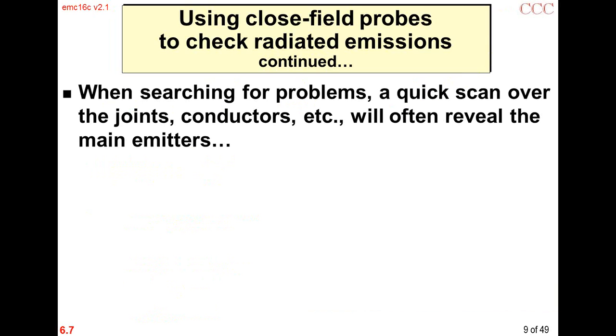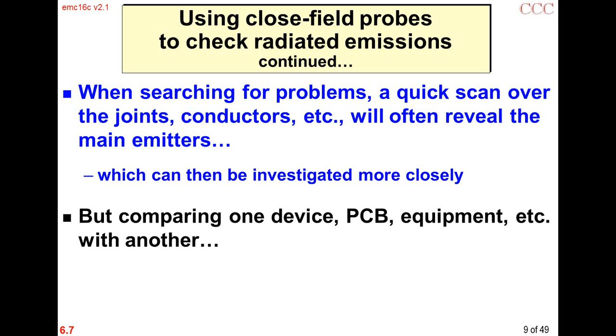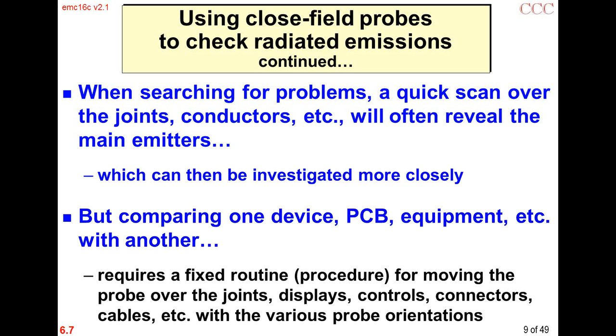If you're looking for problems, a quick scan over the joints and the conductors and things, the cables, will often reveal the main sources of emissions, which can then be investigated more closely. If you're comparing one device or board or equipment with another, then we have to have a fixed routine, a procedure for moving the probe over the joints, displays, controls, etc., using the various orientations. As I said last time, if you remember, probes are very, well, their sensitivity varies depending on where you are on the probe. And so it matters very much how you repeat your holding of the probe. That's why a robot is particularly good, because it'll always repeat what you programmed it to do.